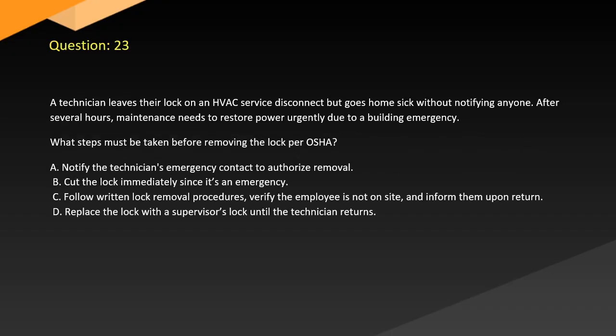Question 23. The technician leaves the lock on an HVAC service disconnect but goes home sick without notifying anyone. After several hours, maintenance needs to restore power urgently due to a building emergency. What steps must be taken before removing the lock per OSHA? A. Notify the technician's emergency contact to authorize removal. B. Cut the lock immediately since it's an emergency. C. Follow written lock removal procedures, verify the employee is not on site and inform them upon return. D. Replace the lock with supervisor's lock until the technician returns.